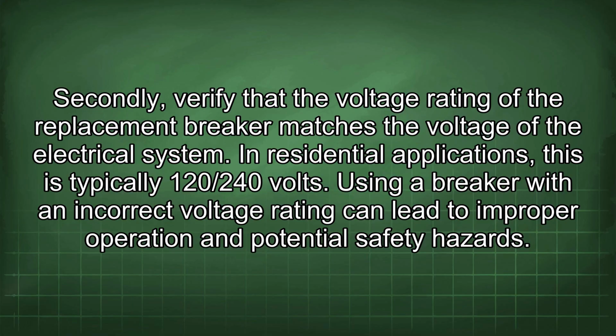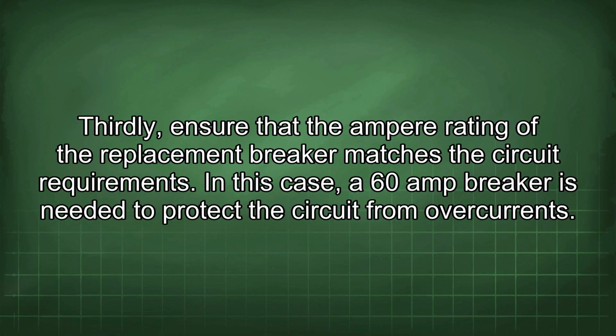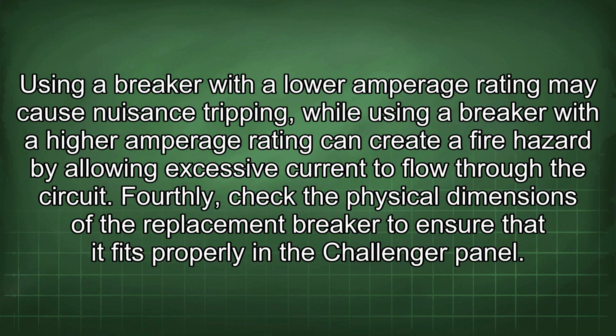In residential applications, this is typically 120/240 volts. Using a breaker with an incorrect voltage rating can lead to improper operation and potential safety hazards. Thirdly, ensure that the ampere rating of the replacement breaker matches the circuit requirements. In this case, a 60-amp breaker is needed to protect the circuit from overcurrents. Using a breaker with a lower amperage rating may cause nuisance tripping, while using a breaker with a higher amperage rating can create a fire hazard by allowing excessive current to flow through the circuit.